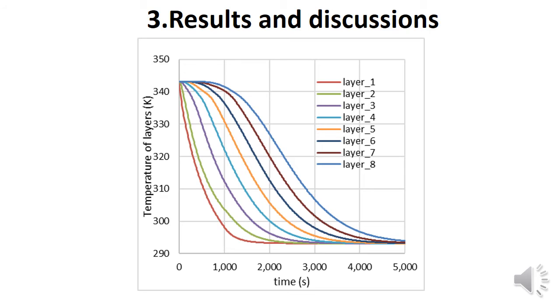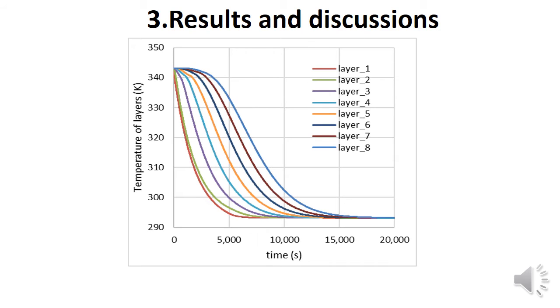The temperature of the top layer has preserved heat during the first 1000 seconds in case of high mass flow, since the temperature stays stable near 70 degrees. In the case of low mass flow, the top layer has conserved the hot temperature until approximately 5000 seconds.